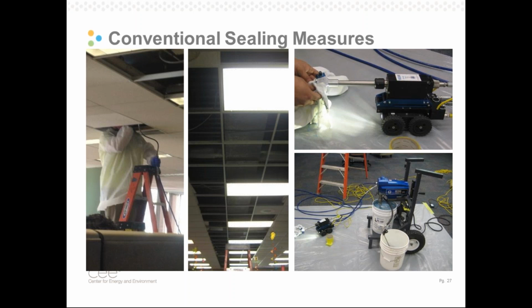On the left, we have a worker who has got a little spray mastic wand that he is waving around up in the drop ceiling, sealing the transverse seams and longitudinal joints from the outside. In the middle, all the ceiling tiles have been taken out along the bottom of a supply duct in preparation for laying a long seam of butyl tape to seal up the longitudinal seam. And on the right, this is the little robot that I spoke about. It has a spray wand that rotates as the robot drives through the ductwork, and it lines the inside of the duct with sealant and seals the joints and seams.